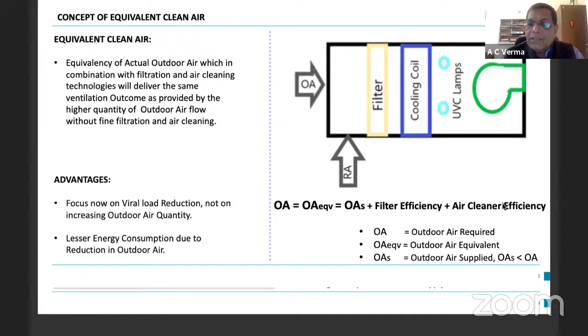And if you see the sketch on the right, this is your AHU, where the outdoor air is coming and the return air is coming. There is a filter, there is a cooling coil, and there is an air cleaning device. Presently we are supplying the outdoor air. This was designed for the minimum outdoor air required, but we have to supply more and more outdoor air. The system does not match with that. So the equivalent clean air approach tells that if this outdoor air is replaced by the outdoor air equivalent, then the problem is solved.